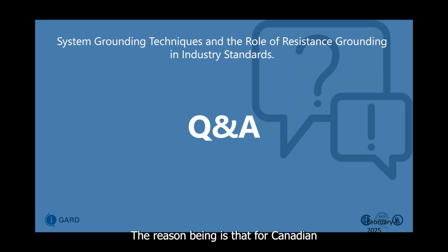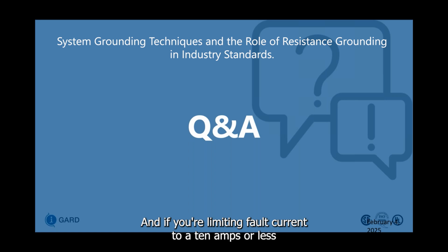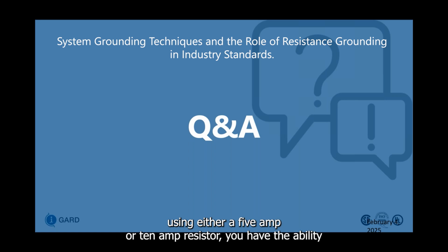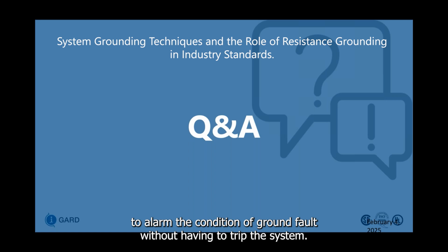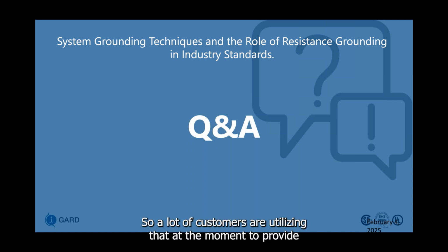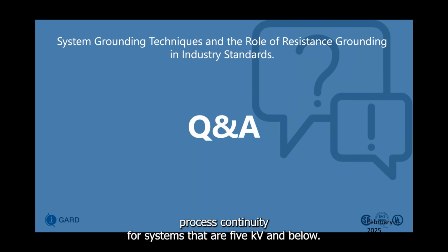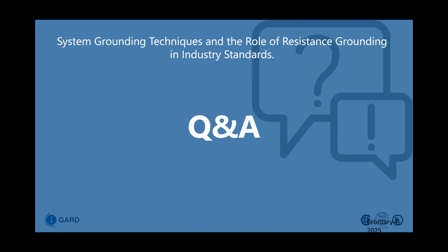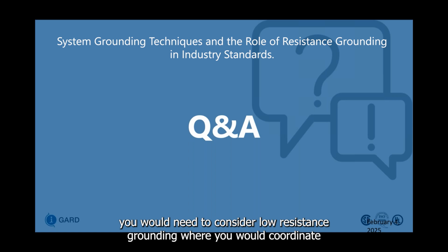The reason being is that for Canadian customers in Table 17, if your system is three-phase three-wire, you're using a continuous rated resistor. And if you're limiting fault current to 10 amps or less using either a 5 amp or 10 amp resistor, you have the ability to alarm the condition of ground fault without having to trip the system. So a lot of customers are utilizing that at the moment to provide process continuity for systems that are 5 kV and below.